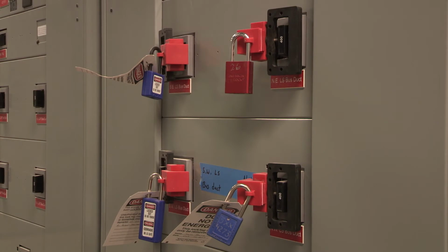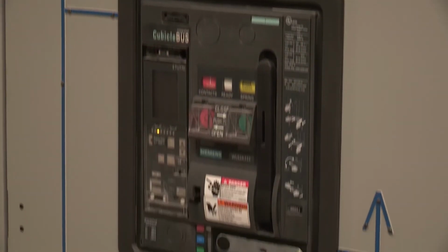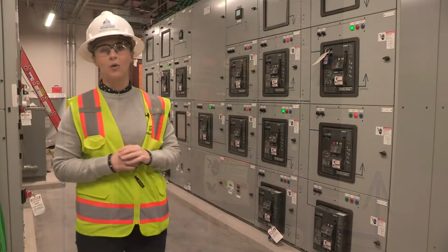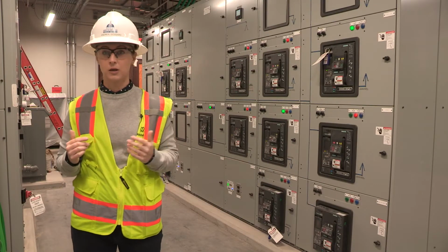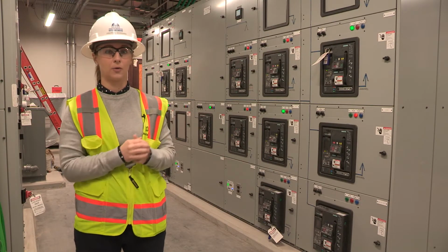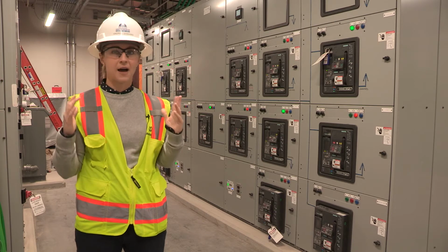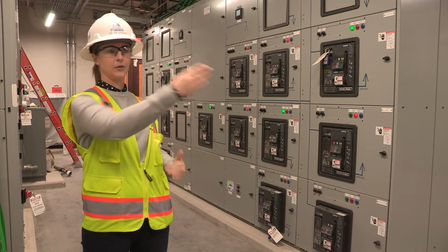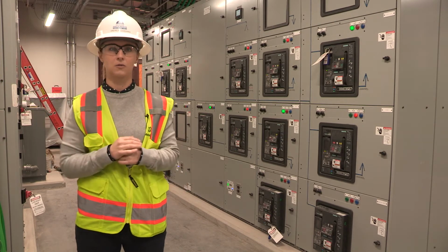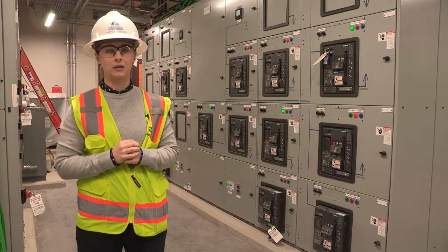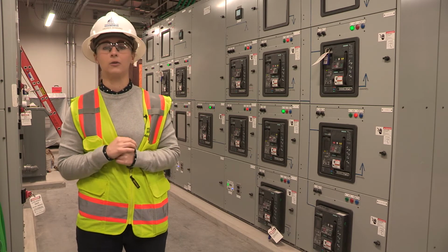This area is a huge leap forward in technology and building management. On that wall we have the automatic transfer switch, which is the go-to for the generator. So three to five seconds after power goes down, those switches make the automatic transfer, and the building would barely notice a power outage on the critical systems.